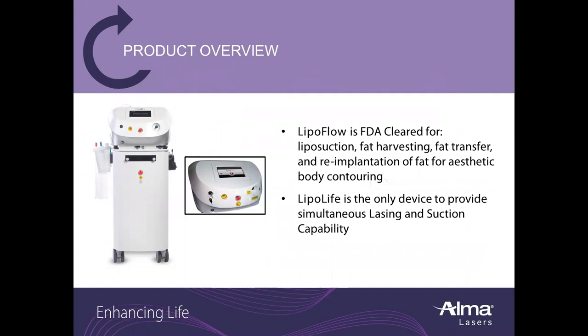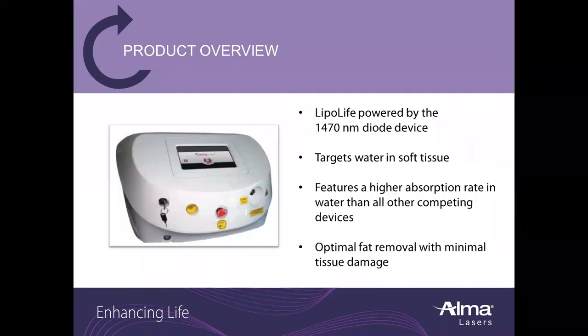LipoLife is the only device to provide simultaneous lasing and suction capability. LipoLife is powered by the 1470 nanometer diode, which targets water in soft tissue and features a higher absorption rate in water than all other competing devices. This makes for optimal fat removal with minimal tissue damage.